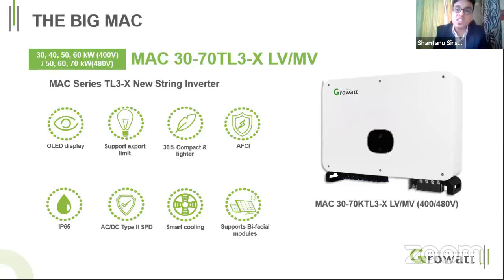As well as with this inverter, we are providing smart cooling, in which we are providing IP68 fans for the cooling of the heatsink, which run at a particular heatsink temperature. These fans are not continuously on, but they get triggered at a particular inverter temperature. As well as for protection, we are providing type 2 SPDs on the AC as well as DC side. Also, these inverters support the zero export limitation with Growatt smart meters.